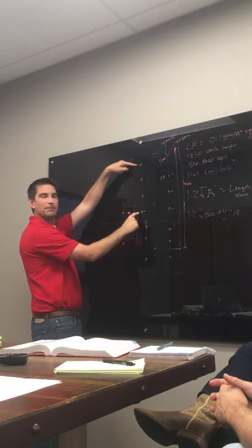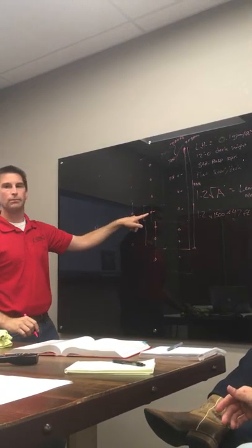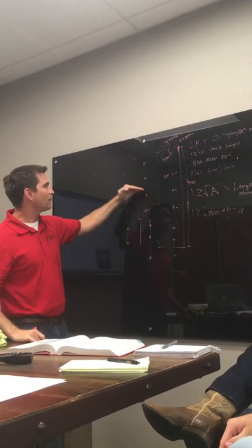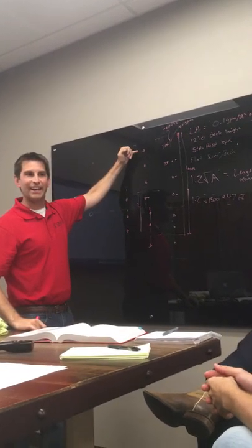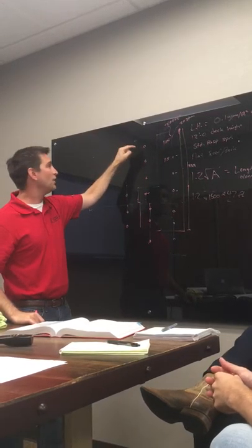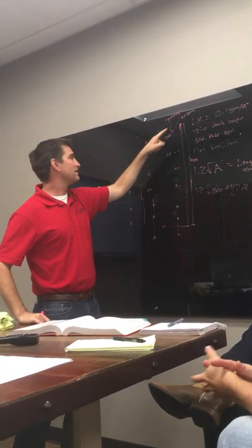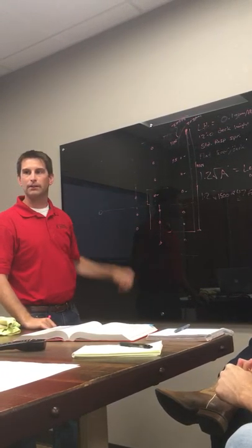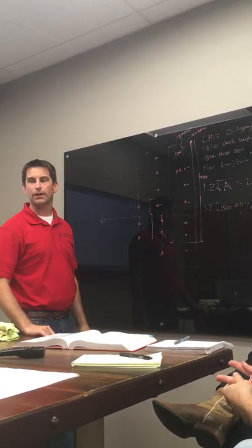And that's why we pick up those heads first, and those are actually more demanding. You're going to flow more water than the one at the end, because I'm going to be losing pressure until I get to that end head, so it's not going to overflow. So it's still going to be more than 20, right? Because it's back further, but it might be like 20.5. So the more pressure you have, the more flow you have.